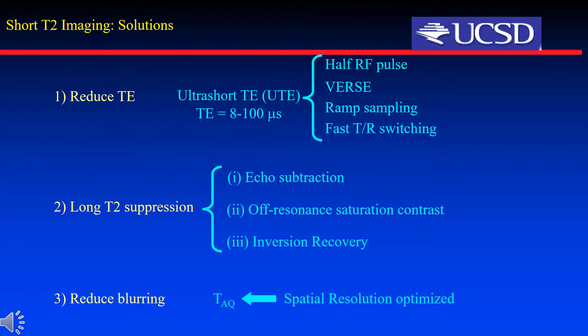The following approaches were employed for short T2 imaging. First, reduce echo time. Ultra-short echo times between 8 to 100 microseconds have been achieved through the combination of half-pulse excitation, variable rate selective excitation, ramp sampling, and fast transmitter-receiver switching. Second, long T2 suppression, including dual-echo subtraction, off-resonance saturation contrast, and inversion recovery pulse techniques. Third, reduce blurring. For short T2 imaging, spatial resolution rather than SNR is typically the limiting factor for clinical application, so data acquisition time should be optimized for spatial resolution.